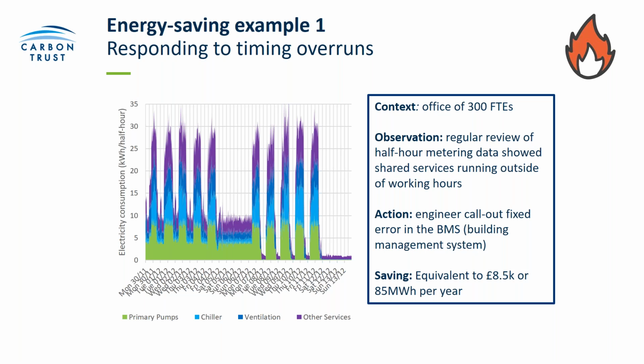Now, when they looked at the first week, so the first 5 spikes that you can see on the graph, you can see that in the evening times, on the dips, there was still quite a lot of energy being used. And when this was looked into, it worked out that there was an error in the building management system that meant that a lot of the pumps and the air conditioning systems were running throughout the night for no reason. So you can see after that weekend and then the next day, this completely reduced.